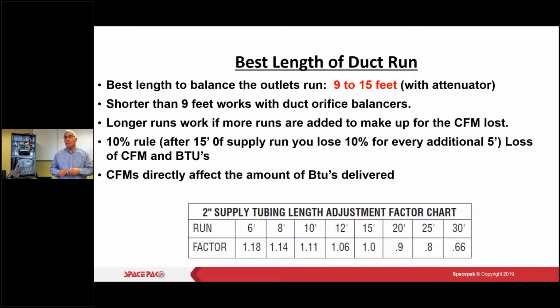So it's the 10% rule after 15 feet, and this is really important. You're going to lose 10% for every additional 5 feet in CFMs and BTUs. So again, if you're looking at a job and you're trying to do SpacePak, and I've got a 50-foot run to get to this room with my 2-inch outlets, and by calculations I only need 2 outlets, you may now need up to 4, 5, possibly 6, depending on what you're trying to deliver there. And now I've got to get all those outlets in that room. A lot of times I'm only coming into that room in one little corner. Doesn't look too good. So possibly you don't use that room in the SpacePak. Maybe you use it as a mini split room or something. But these are the rules you have to adhere to.